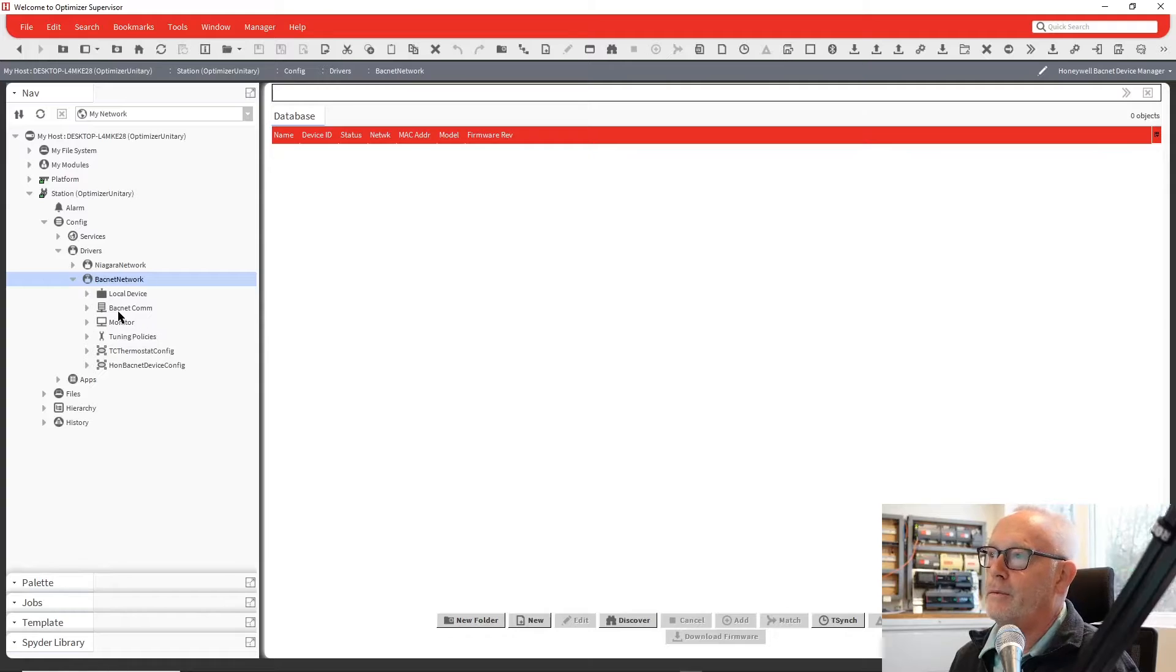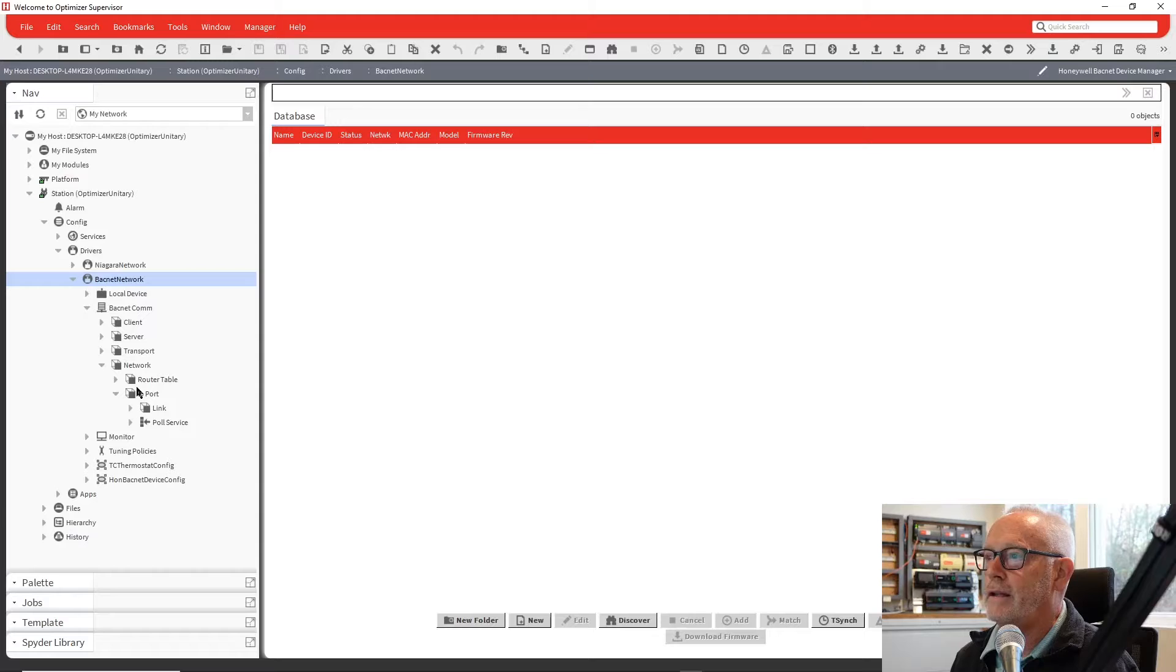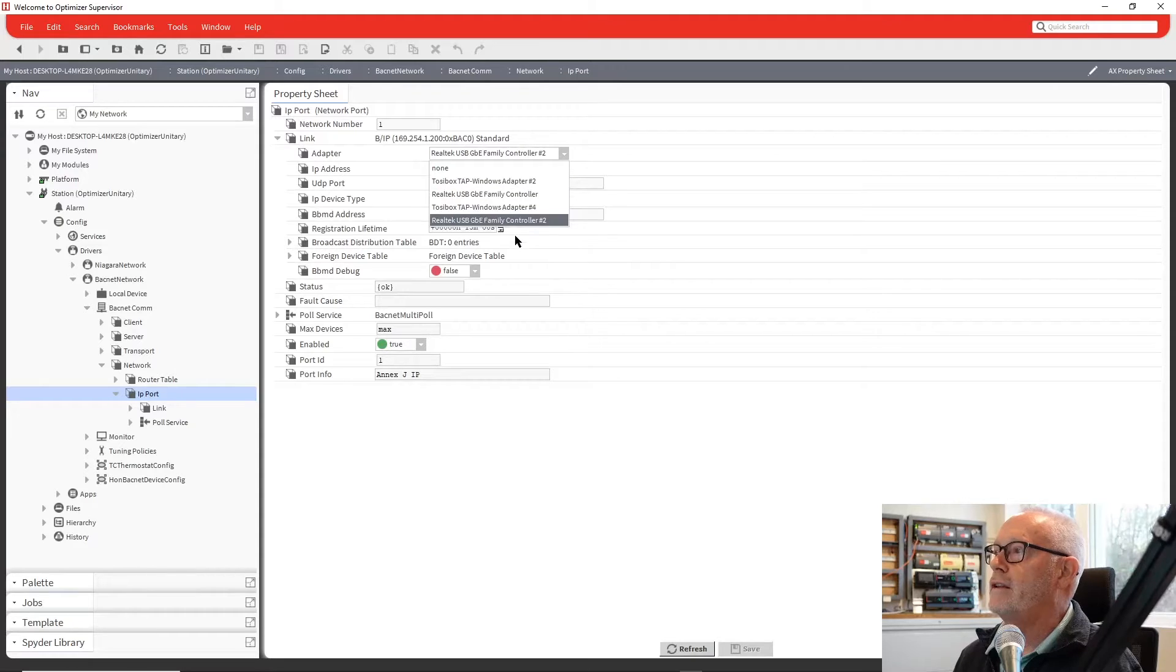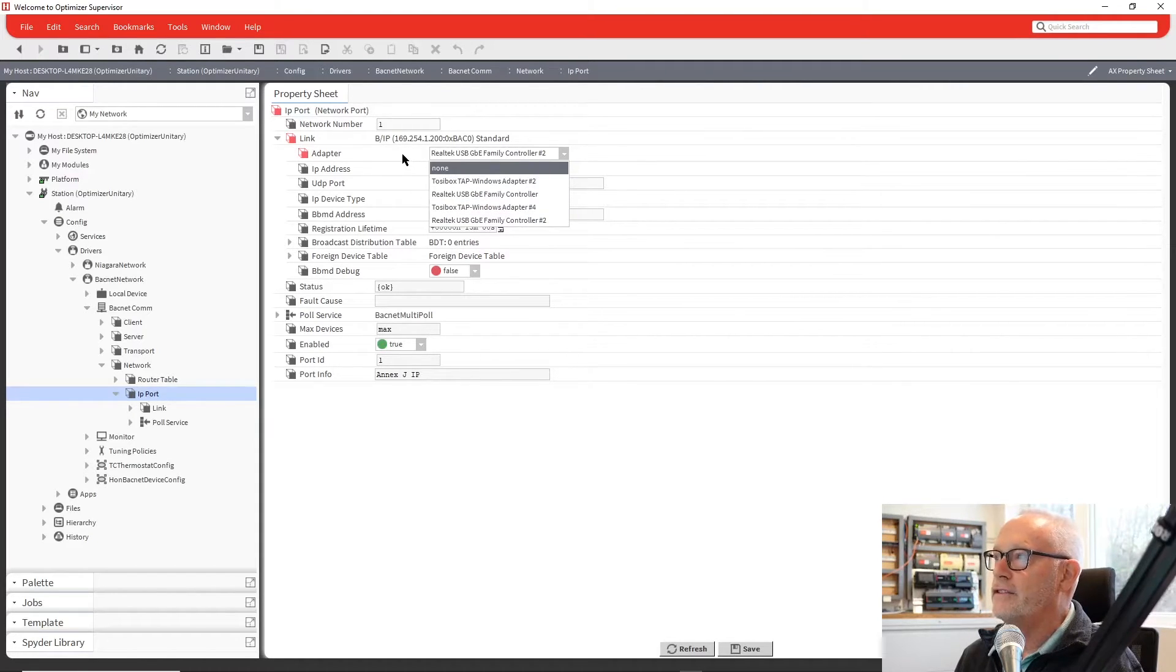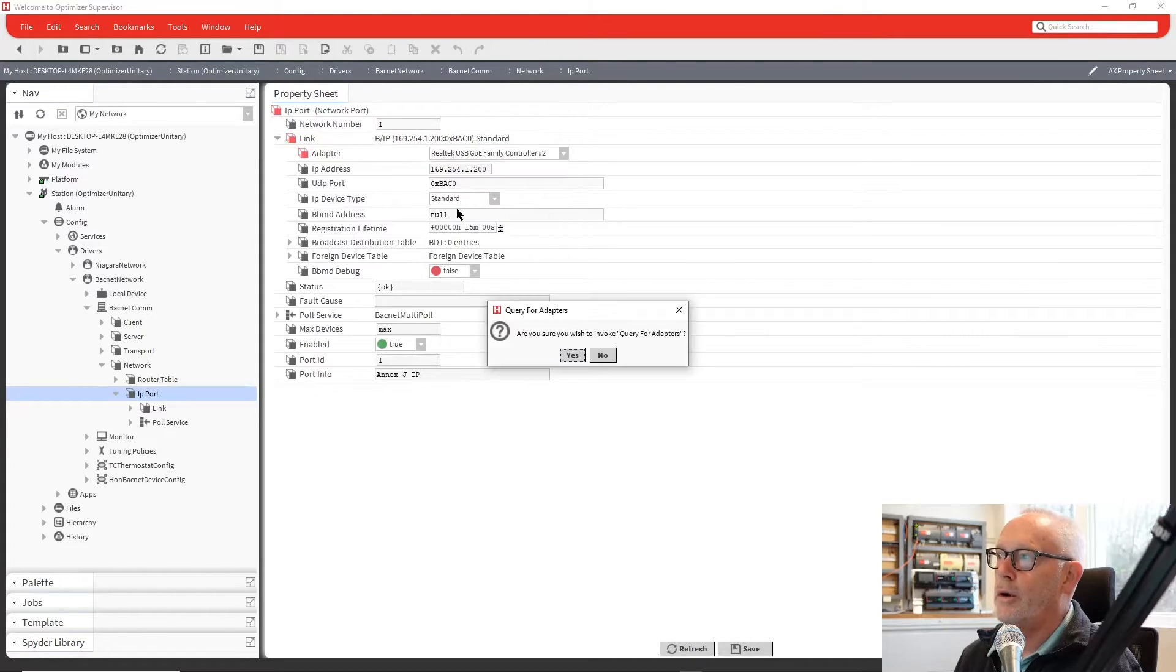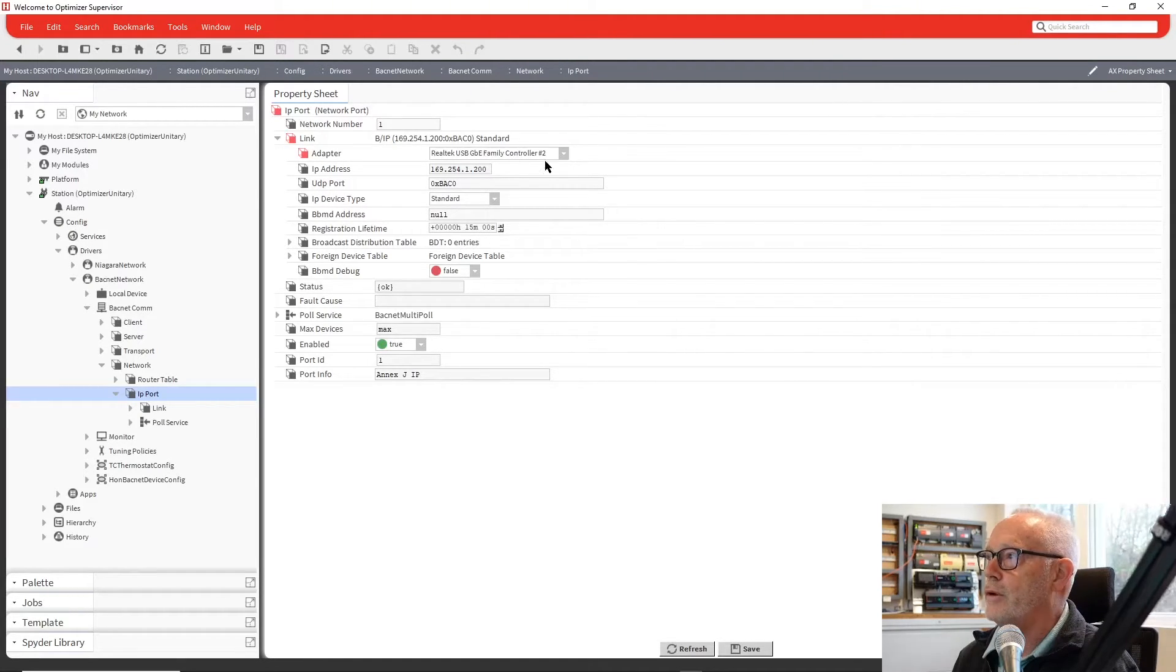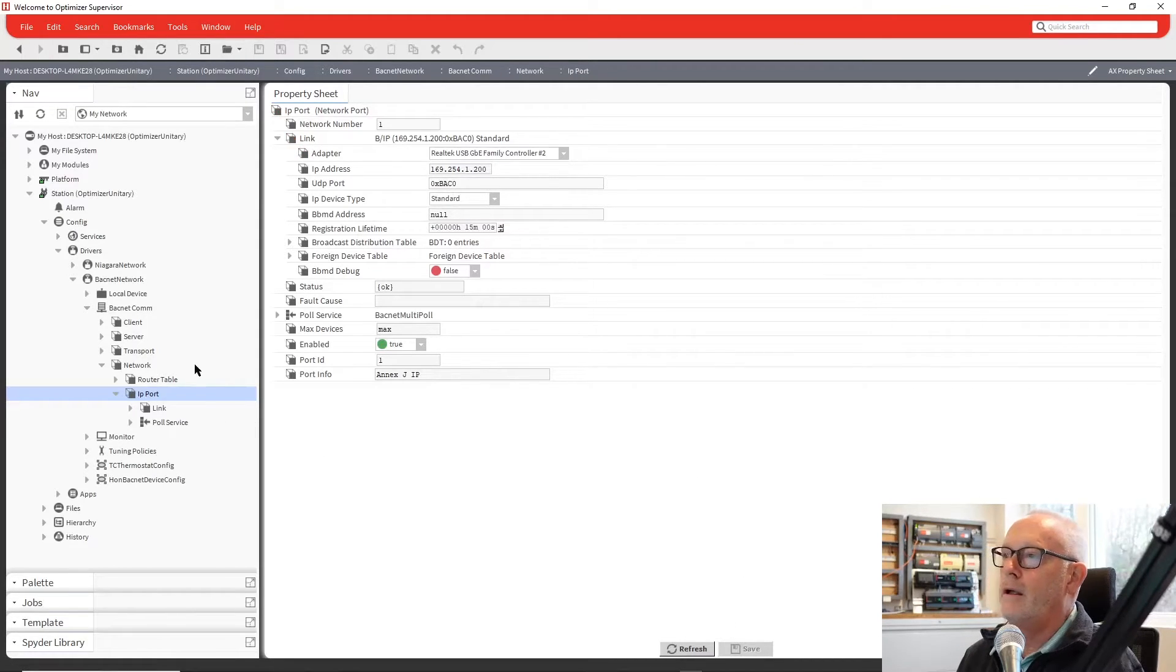Obviously, when you work with BACnet IP, you have to make sure you have your link set up correctly. So if we go into the IP port, go under link, I'll make sure that I'm set up there correctly. And I do have that one. You can see by the IP address. If you set your address on your computer, but when you go here to the adapter and you don't find it, or you find it and it doesn't come up with the IP address, just right-click on link actions and then do a query for adapters. It will go out and recheck all the Ethernet ports on the computer. And then you can select it, and it will show the right address there.